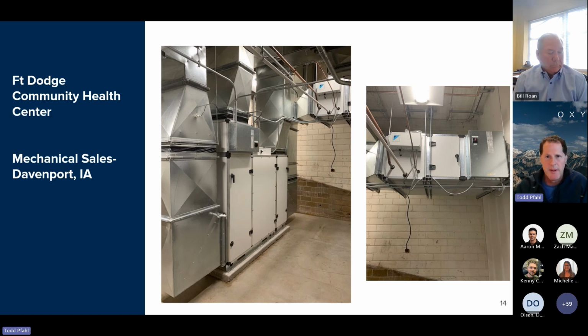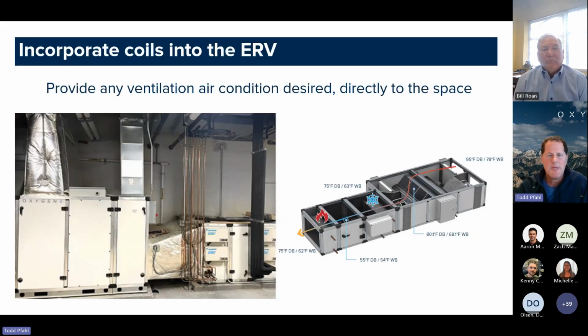And here we're using a heat pump, a VRV heat pump that's doing the heating and cooling of the outside air, and then an SCR controlled strip heater, electric heater, to do some trim heating, dehumidification, or backup heating. But again, we probably would not have been able to fit a total package unit into this small space. It's actually down in a basement in a project in Iowa.